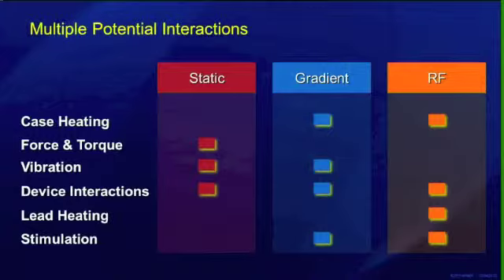Now, even with non-conditional device leads, more recent leads tend to have fairly moderate heating at the tissue in in vivo animal studies, but still this is a major concern. Similarly, the dynamic field, the gradient field, or RF can produce stimulation through the lead itself, with or even without having a device hooked up to the system.